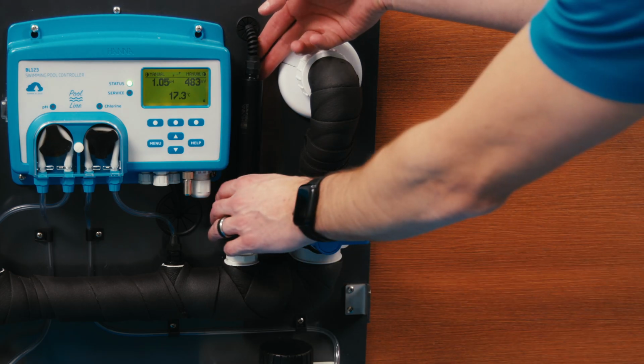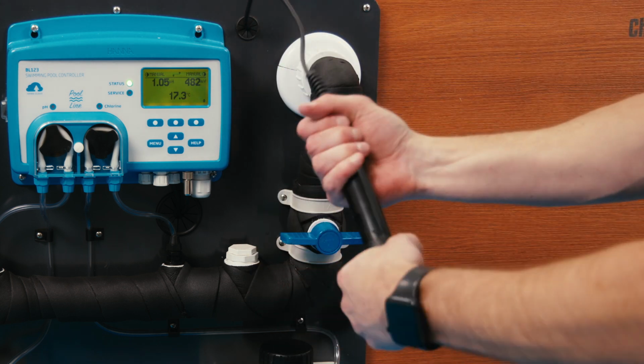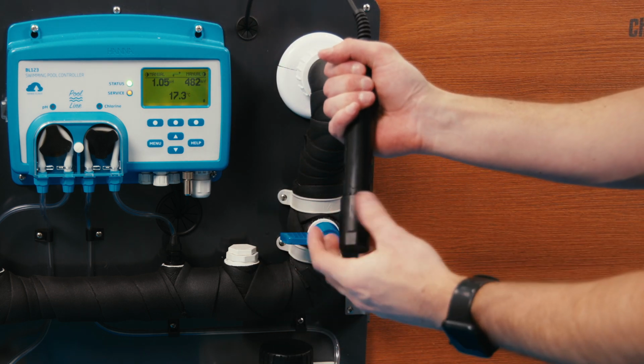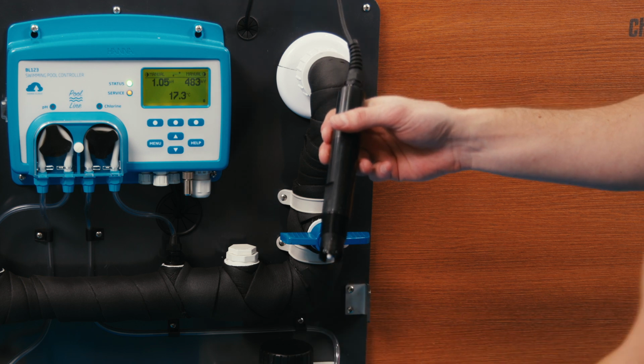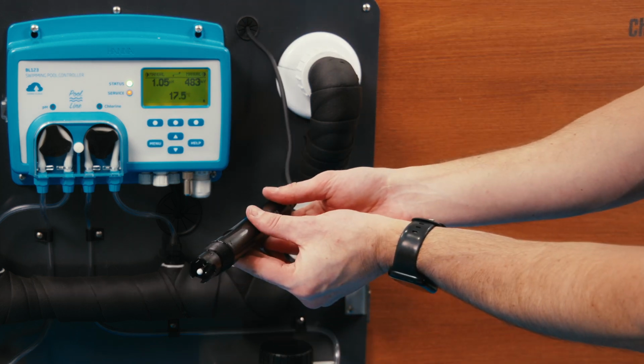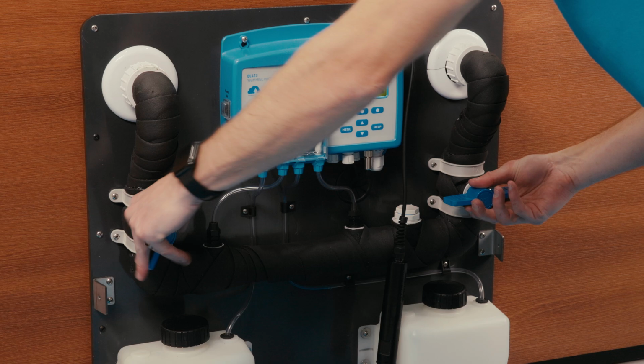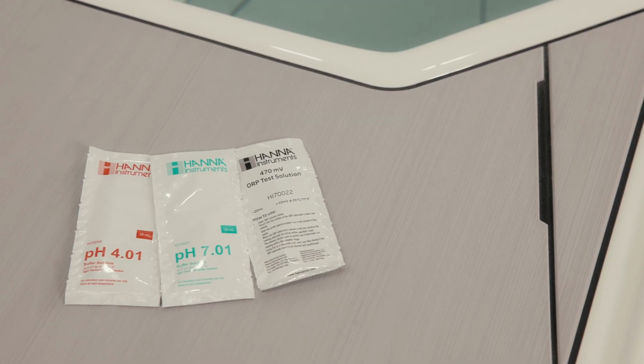During this process, try not to leave the probe dry for more than a few minutes. Moving steadily through the steps helps protect the sensor and gives you an accurate calibration. With the probe free in your hand and the valves reopened, you're ready to start. We'll start with the pH calibration.